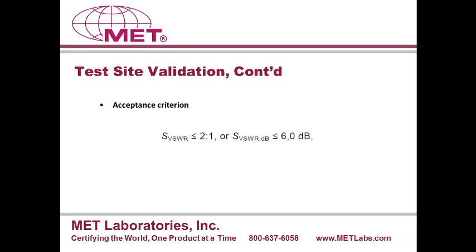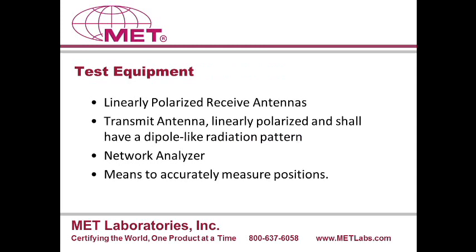The next slide gives you the acceptable criteria. In linear terminology, the acceptable ratio is two to one. In dB terminology, all the reflections should be less than six dB for a site to be accredited according to CISPR 16-1-4. The calibration procedure is very involved and requires a lot of skill and knowledge. The test equipment used is based on a linearly polarized receive antenna like the one used in the lab environment for above one gigahertz testing every day — a common example would be the EMCO 3115 or a similar antenna, which is a double-ridged horn antenna covering the frequency range from one gigahertz to 18 gigahertz.